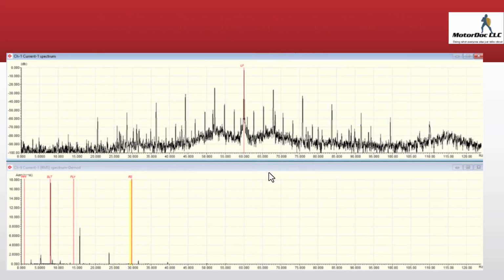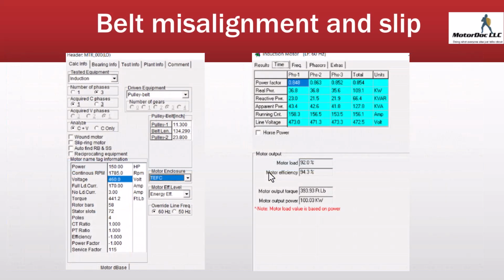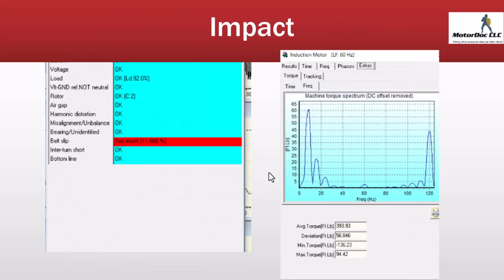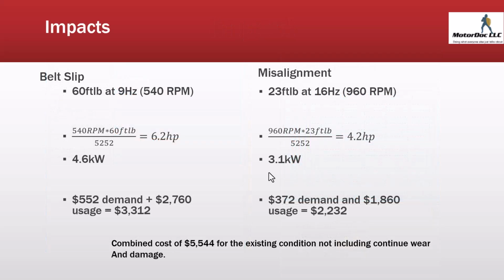And we'll just say those are all frequencies associated with a belt. So we take a look at this one, 109.1 kilowatts coming in. We've got about 12% slip. And we calculate everything out. Now this one is far more severe. So we're looking at a total of about $5,500 or $5,600 almost worth of losses.